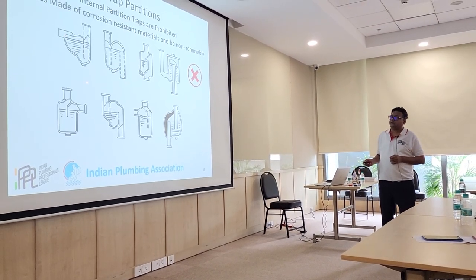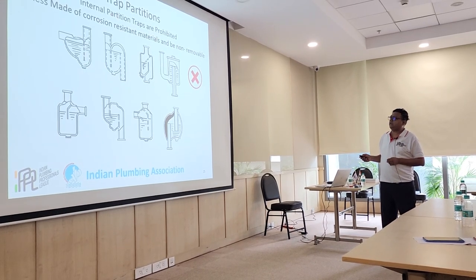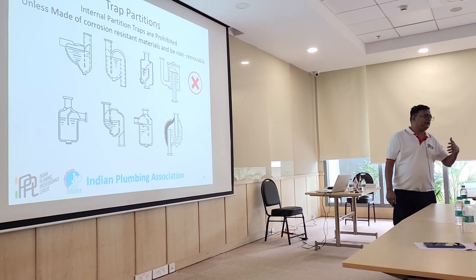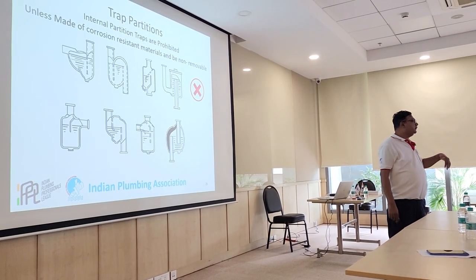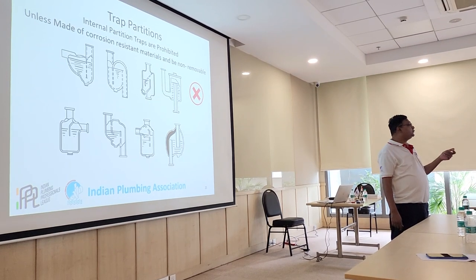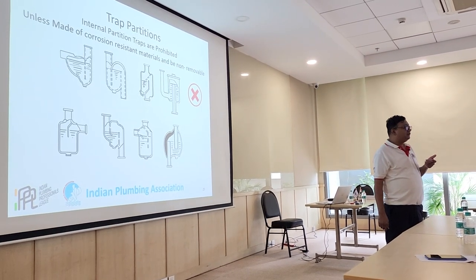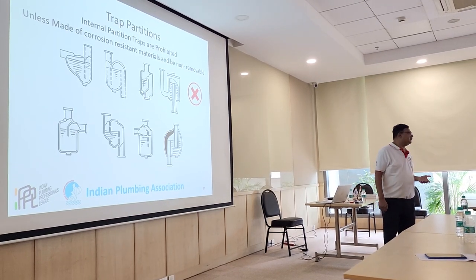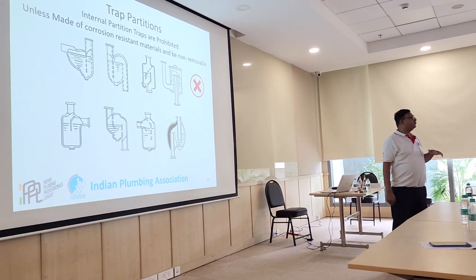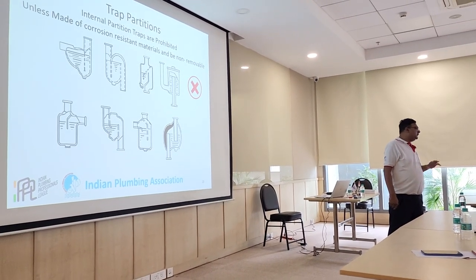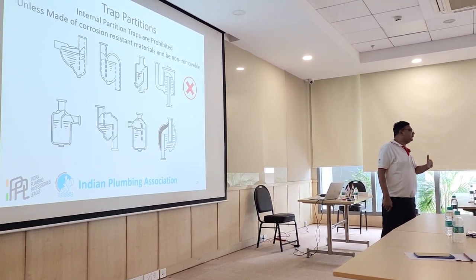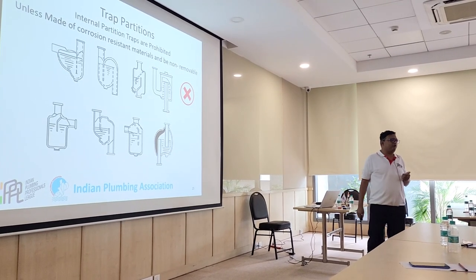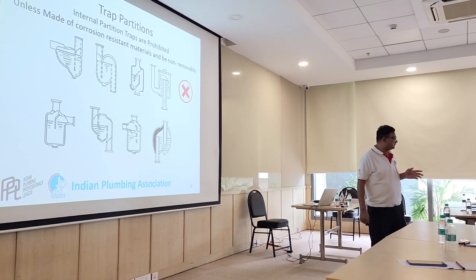Trap partitions. Internal partition traps are prohibited. As I said, trap should, what was the sentence? Trap should allow the water to flow smoothly, or it should be self-cleansing. What was the term? Self-cleansing. But if you put such a thing, will it be self-cleansing? Most of the cases it will not, unless you have a very huge flow coming in a very short span of time. So it will not give its optimum performance of self-cleansing. Okay?